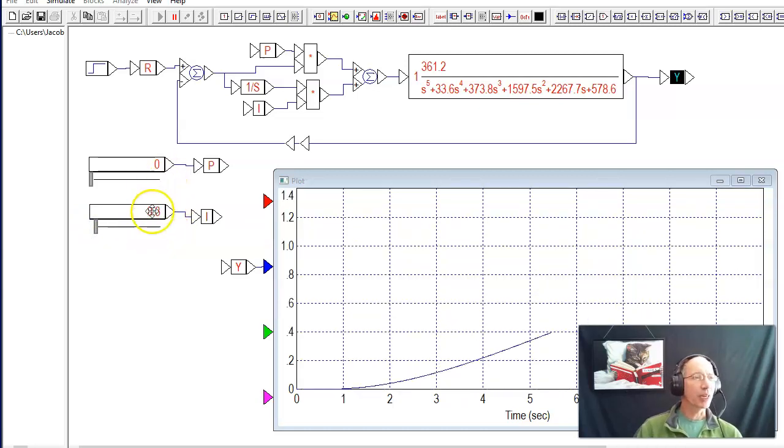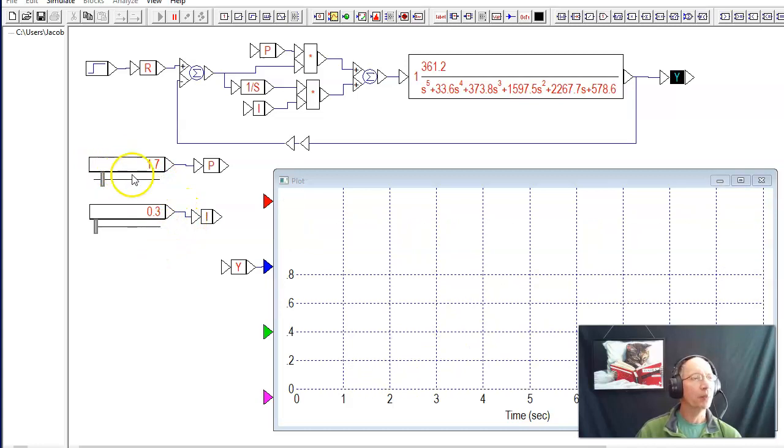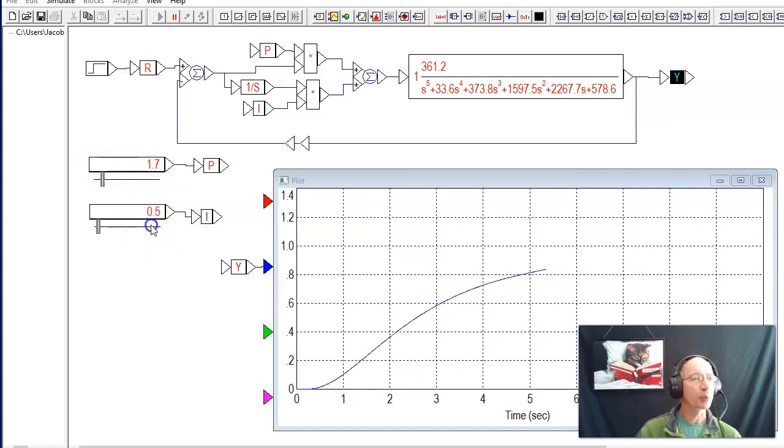To play with two knobs, I would iterate between the two. I'll get 20% overshoot with I, get rid of the overshoot with P. P kind of looks like friction. Then, I's kind of like a spring. Make the spring stiffer. I get overshoot back. Now, add friction to get rid of it. And notice there's kind of a sweet spot. I want to get the overshoot as low as possible.